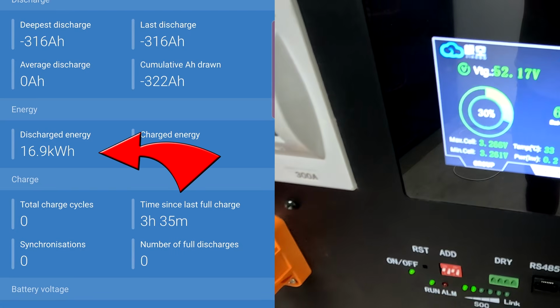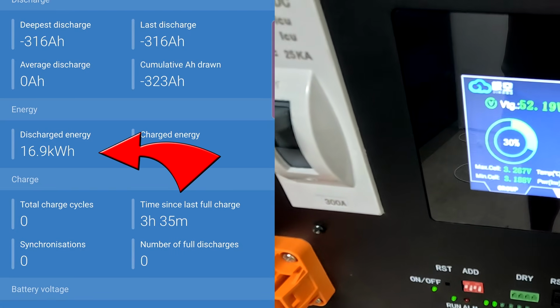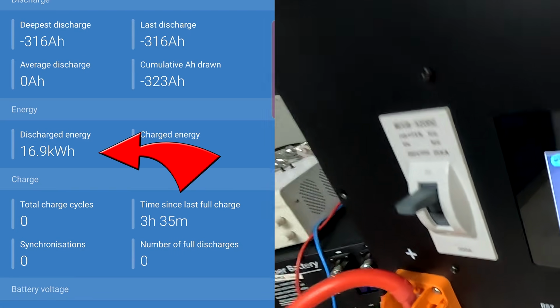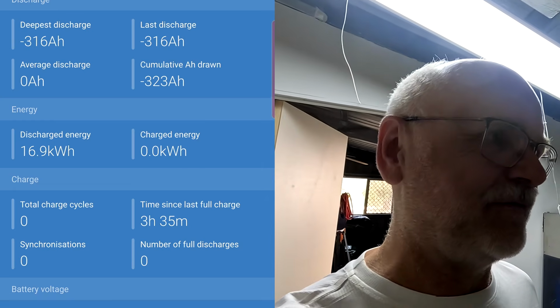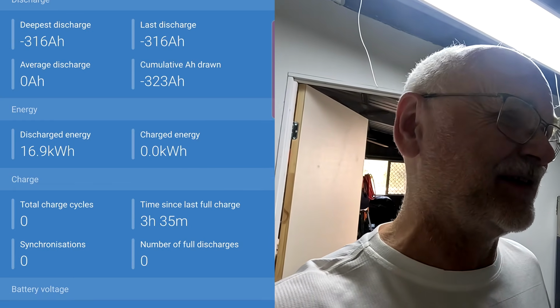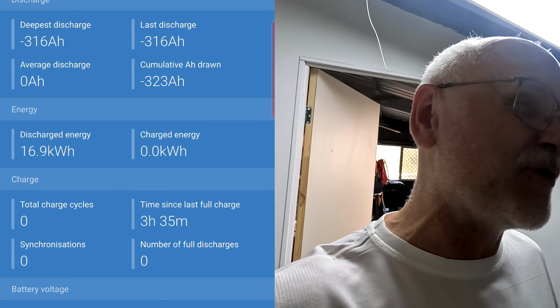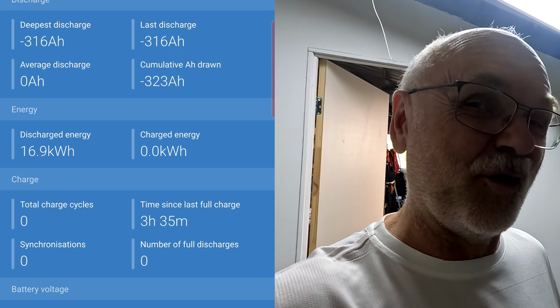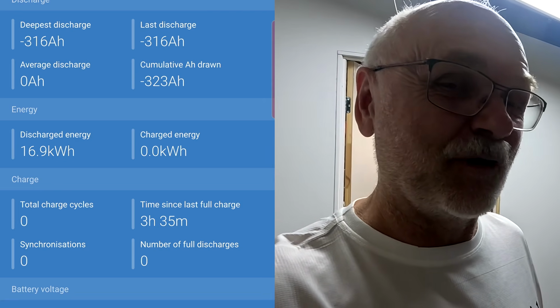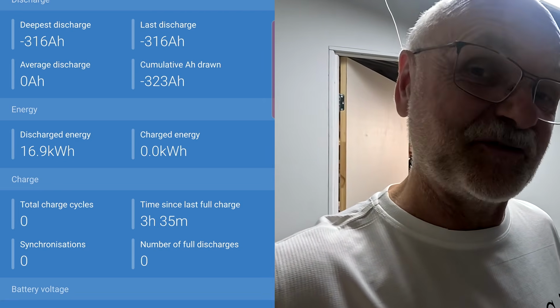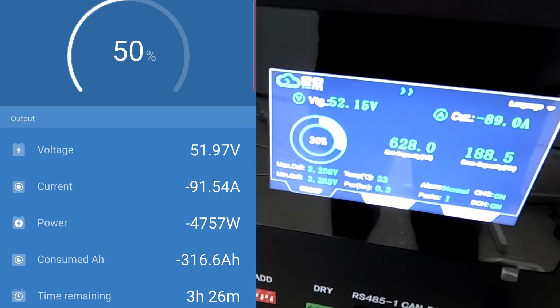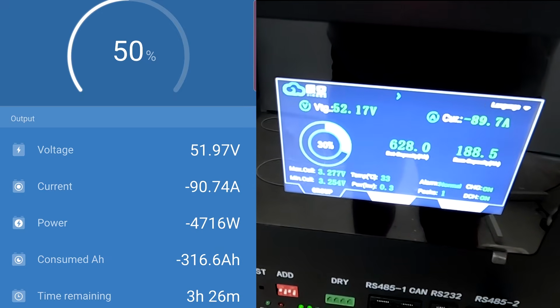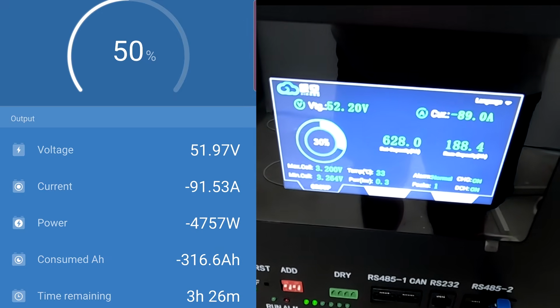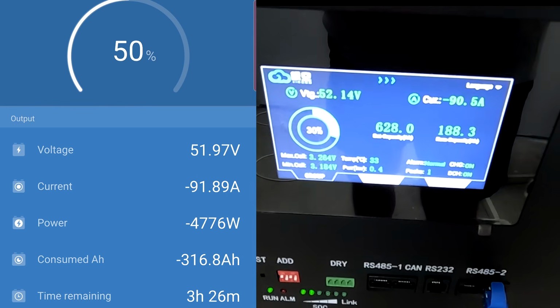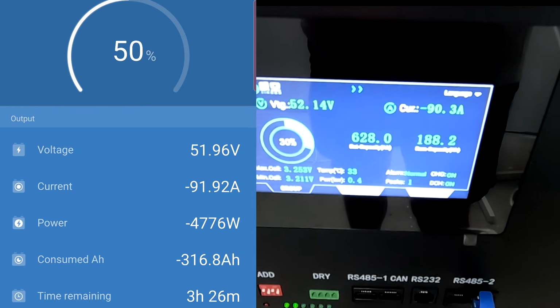So we have drawn 16.9 kilowatt hours at 50% state of charge. That means we get another 17 kilowatt hours out of it until it's empty, so we are getting close to 34 kilowatt hours out of one single battery. That is pretty cool. So we are just under 52 volts, discharging with 90 amps, 4.7 kilowatts, and another 3 hours and 26 minutes to go.